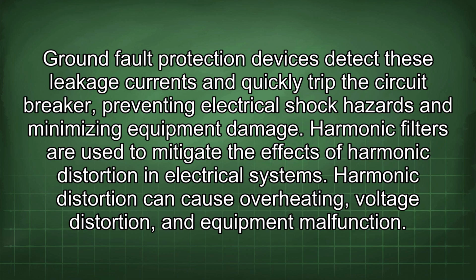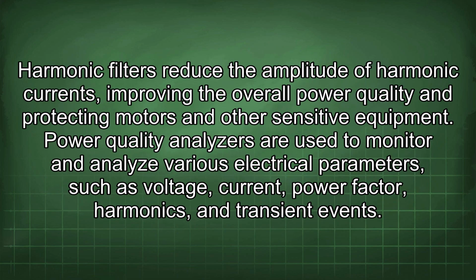and minimizing equipment damage. Harmonic filters are used to mitigate the effects of harmonic distortion in electrical systems. Harmonic distortion can cause overheating, voltage distortion, and equipment malfunction. Harmonic filters reduce the amplitude of harmonic currents, improving the overall power quality and protecting motors and other sensitive equipment.